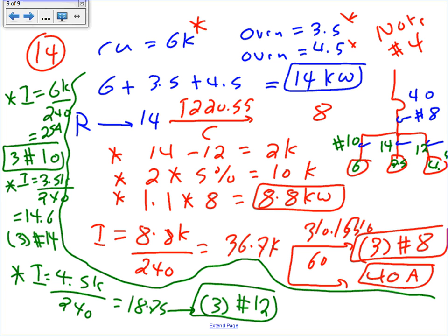That's why I took this example, just to show you how you can have 14, 12, and 8 tied together in one box, feeding all these equipments, and the overcurrent protection device is 40, that's okay. There's a distance limitation. Yeah, but that's why they say close proximity in a residential. How far would that be? I mean, yeah, it could be. For this one it's okay. Otherwise, you're going to go to the rules of the tap, guys. There's the 10 foot rule and the 25 foot rule.